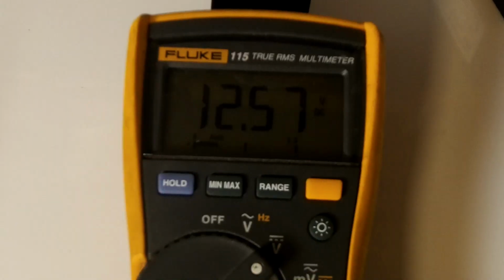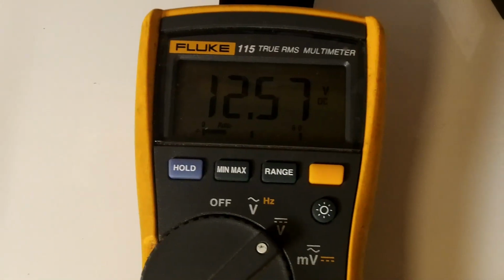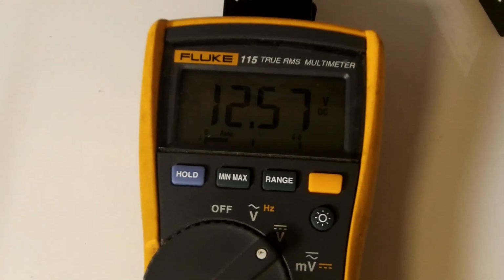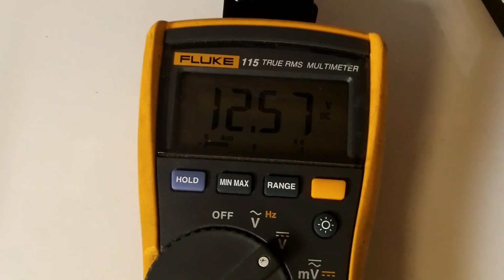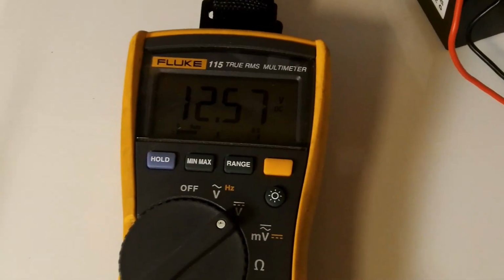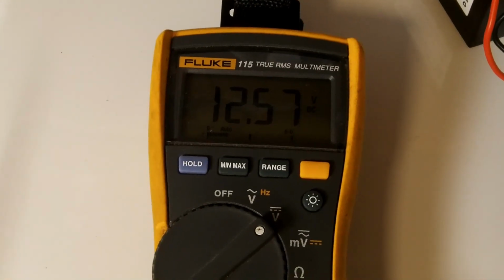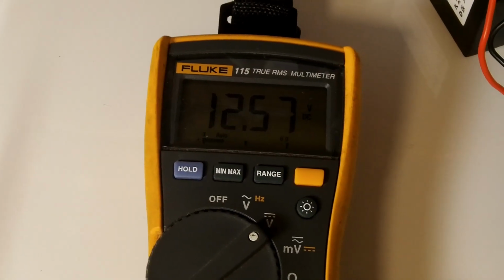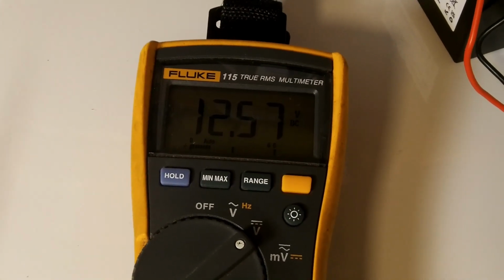Testing the leads here, the battery voltage is 12.57 volts. So it looks like it shut down the current coming out, but then it reset itself and is now letting voltage come back out again, though it's definitely well lower than it should be. So it looks like maybe the cutoff was real close to that 14 volt level.